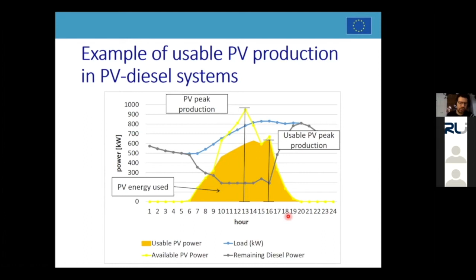We said that 30% operational capacity is the minimum for the diesel generator, so this can't be reduced further, and there's also a minimum rotating mass required according to the current load. So even if we theoretically have full coverage of the load by PV, we still need to run the diesel generator. This shows it's not only about shifting excess energy to the evening with a battery, it's also about increasing directly usable PV power by enabling the diesel generator to switch off. So this is an important function of a battery.